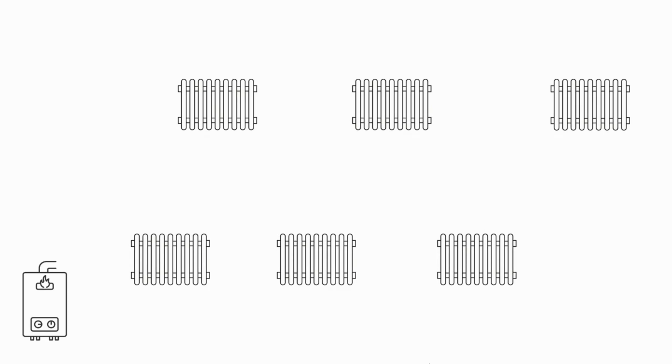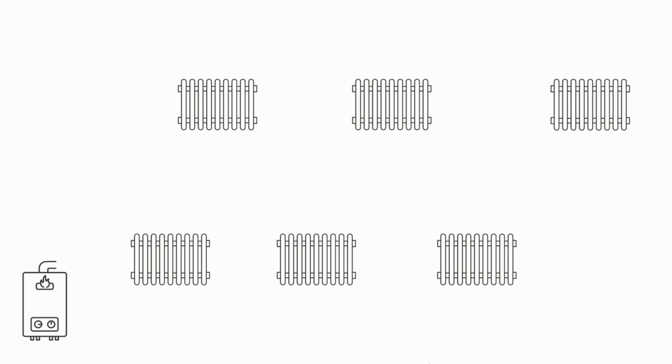They're all likely to be different sizes to accommodate the output requirements of the respective rooms and they're all going to have different lengths of pipework feeding them from the flow and return from the boiler. What that all amounts to is that no two radiators are the same in terms of their resistance to flow.